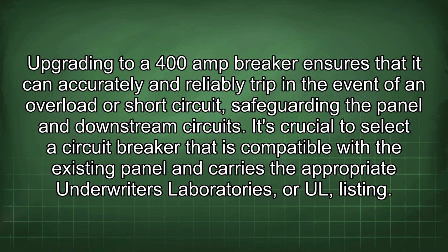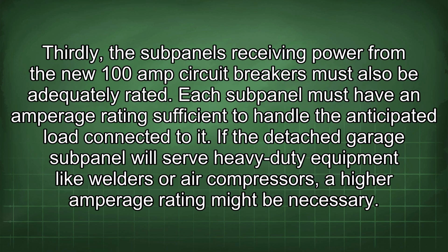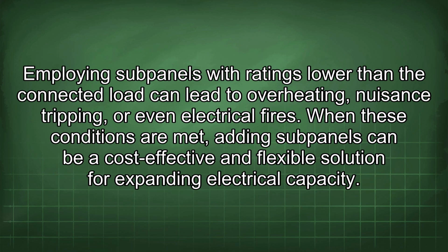Thirdly, the subpanels receiving power from the new 100 amp circuit breakers must also be adequately rated. Each subpanel must have an amperage rating sufficient to handle the anticipated load connected to it. If the detached garage subpanel will serve heavy-duty equipment like welders or air compressors, a higher amperage rating might be necessary. Employing subpanels with ratings lower than the connected load can lead to overheating, nuisance tripping, or even electrical fires.